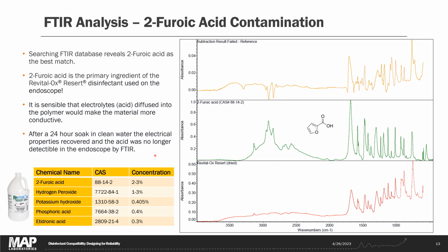It makes a lot of sense that having an acid in our polymer would make it more conductive. Those ions make the material more conductive. We found that after soaking the endoscope in water for 24 hours, the acid diffused out of the endoscope. We were no longer able to detect it by FTIR, and we then passed the electrical leakage test.